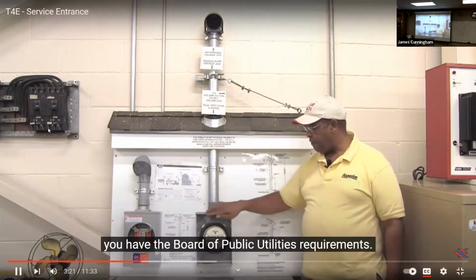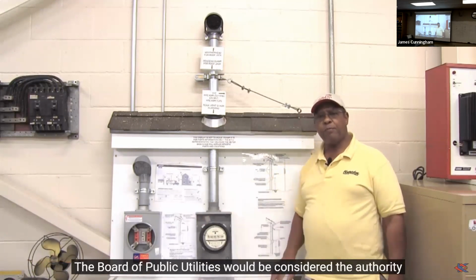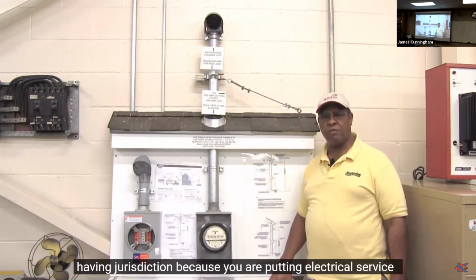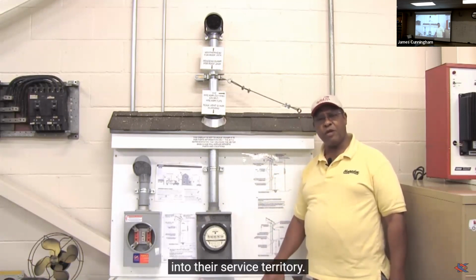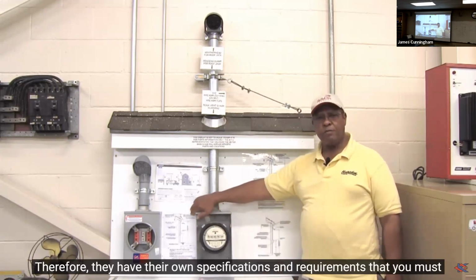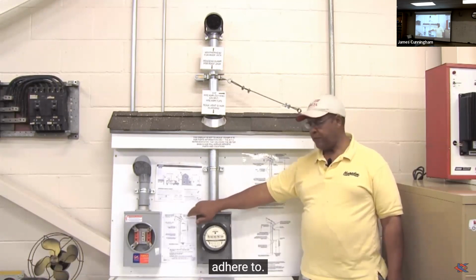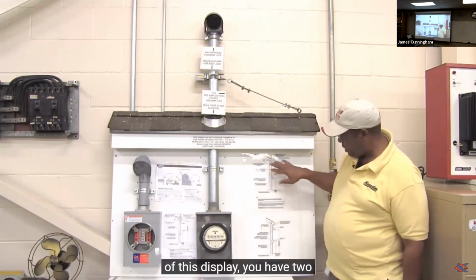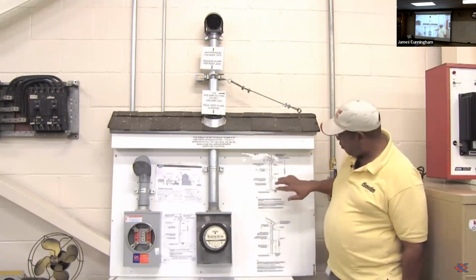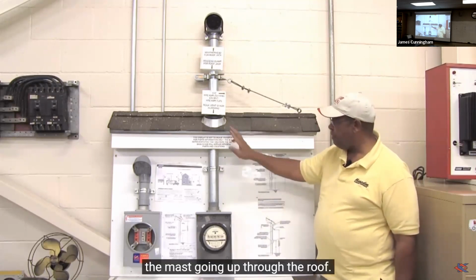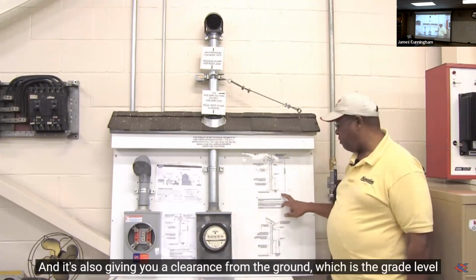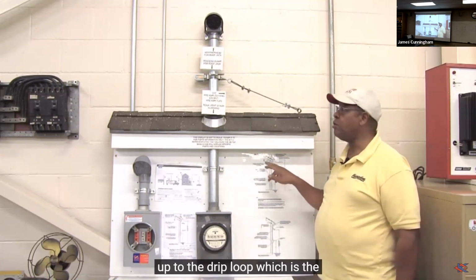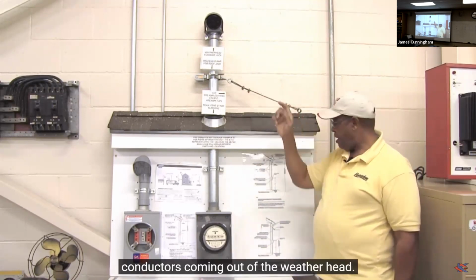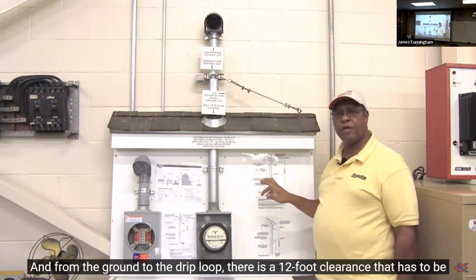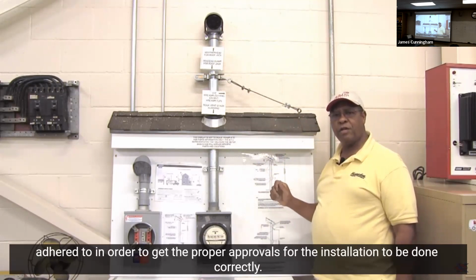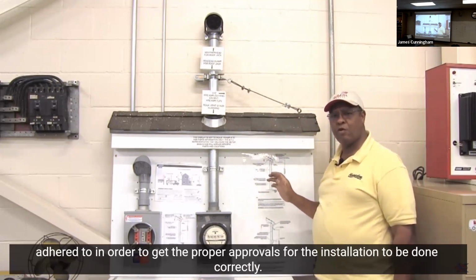And then below it, you have the Board of Public Utilities requirements. The Board of Public Utilities would be considered the authority having jurisdiction because you are putting electrical service into their service territory. Therefore, they have their own specifications and requirements that you must adhere to. And then over on this page of this display, you have two types of displays. The one at the top is showing you the mast going up through the roof. And it's also giving you a clearance from the ground, which is the grade level, up to the drip loop, which is the conductors coming out of the weatherhead. And from the ground to the drip loop, there is a 12-foot clearance that has to be adhered to in order to get the proper approvals for the installation to be done correctly.